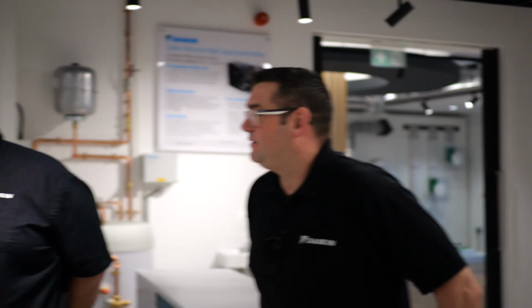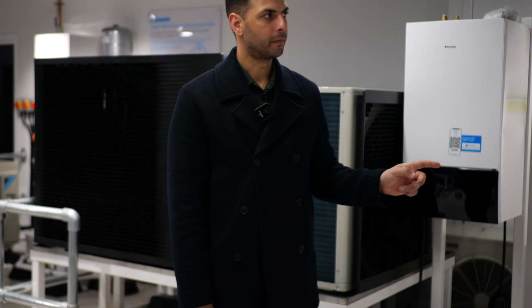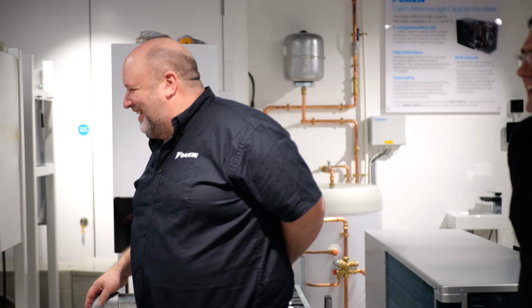I see. Going back to the HT, so the biggest one you do is a 14? It's 18. The biggest you do is an 18? Yeah. The biggest bugbear within the industry is people will say a size 16 kilowatt heat pump. It's 16 kilowatt at 7 degree ambient and a water flow temperature of 35. So you need to take into account what the actual capacity of that heat pump is.